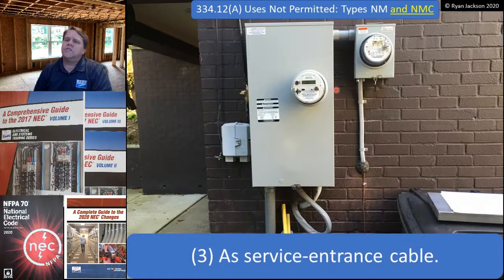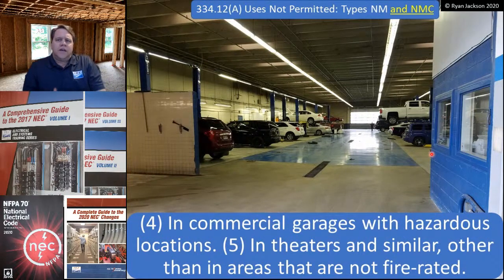Number three, you can't use it as a substitute for service entrance cable. I know depending on where you live in the United States, you look at this and your head explodes. In Utah, where I live, you would never see this. But in some parts of the country, this is everywhere. My friend Sean from the DC area sent this. This is SE cable, and so is this down here. What this rule is saying is, look, you can't use NM cable as service entrance cable. Okay, fine. You cannot use it in commercial garages that have hazardous locations. That makes sense. I mean, it probably has some physical damage concerns and different things.